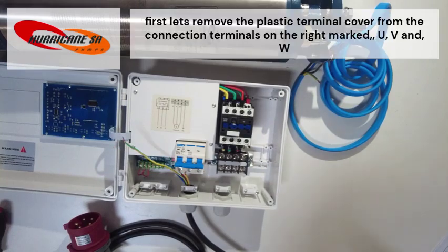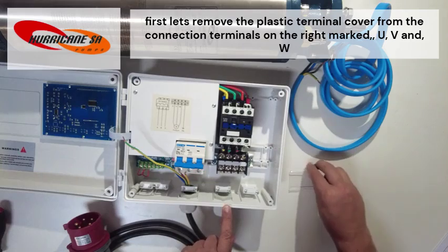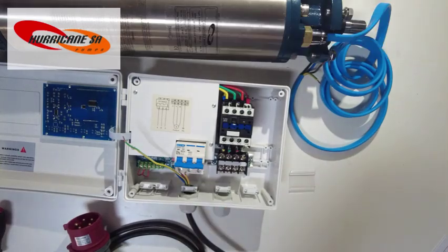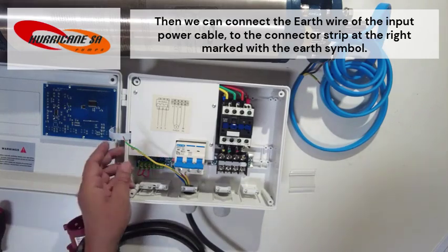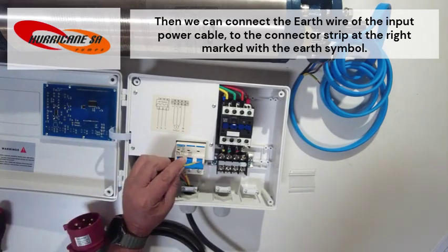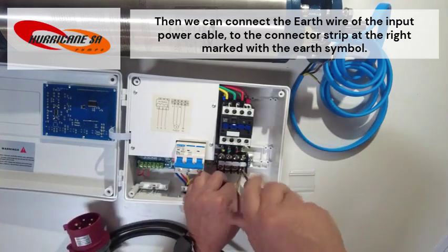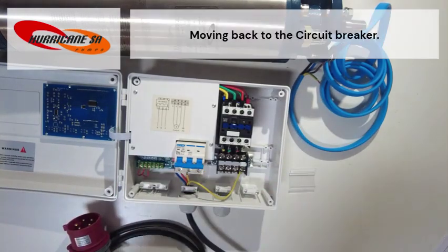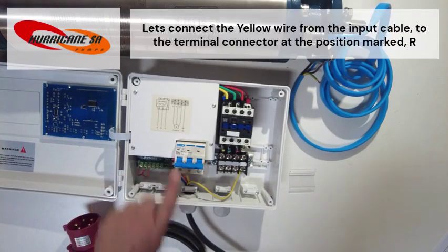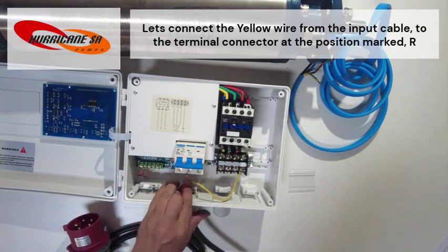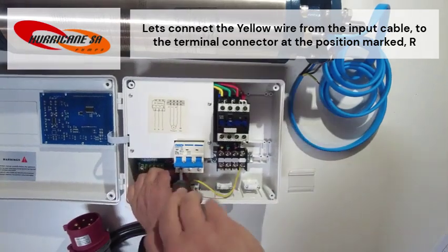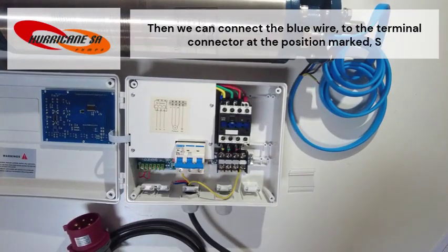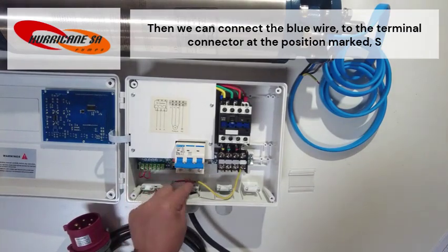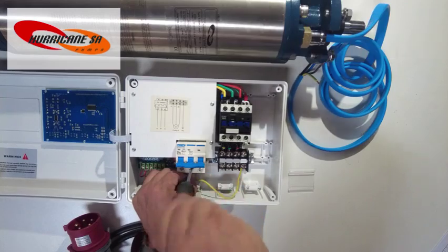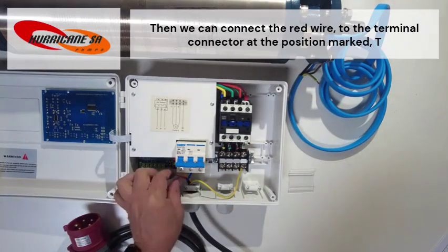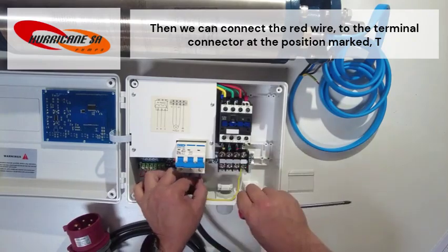First, let's remove the plastic terminal cover from the connection terminals on the right marked U, V, and W. Then we can connect the earth wire of the input power cable to the connector strip at the right marked with the earth symbol. Moving back to the circuit breaker, let's connect the yellow wire from the input cable to the terminal connector at the position marked R. Then we can connect the blue wire to the terminal connector at the position marked S. Then we can connect the red wire to the terminal connector at the position marked T.